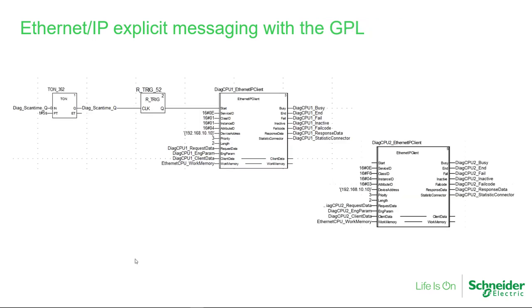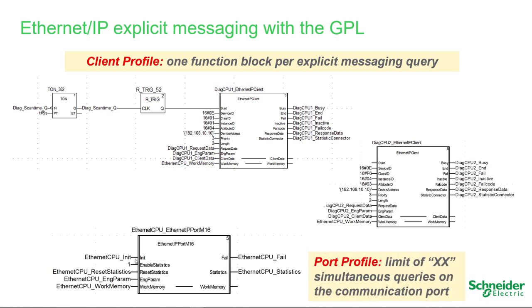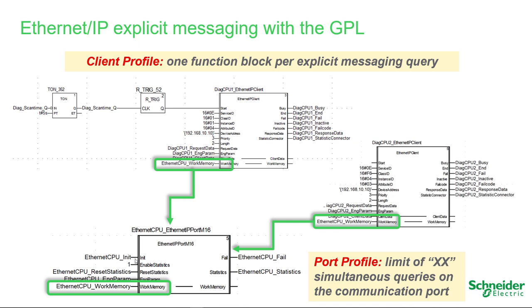For the general purpose library, when using Ethernet IP explicit messaging, you combine two types of function blocks. One is the client profile function block, of which you typically have one instance for each type of query with its class, instance, and attribute parameters. All client function block instances are connected through a work memory variable, and all communications are managed by a single port profile function block that controls the number of simultaneous queries active at a given time.